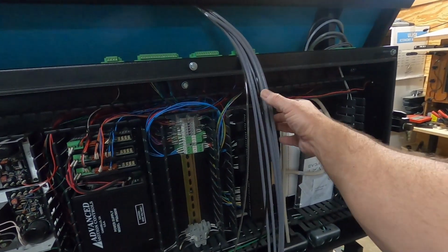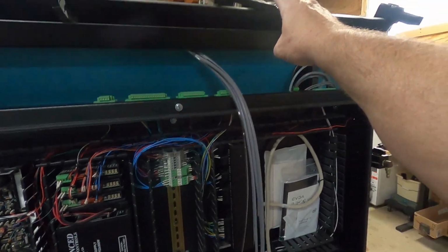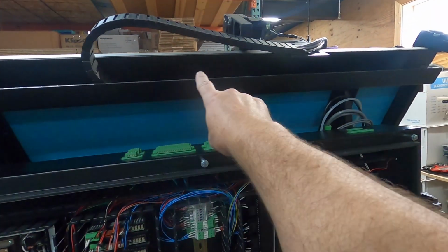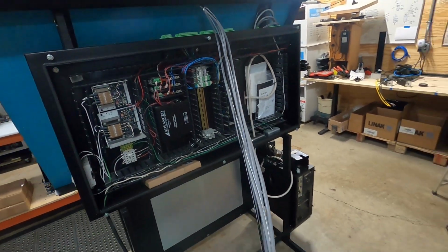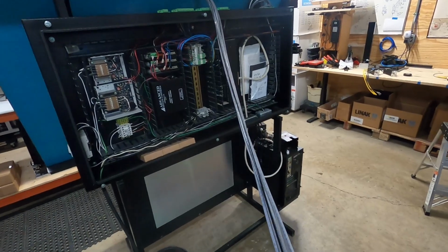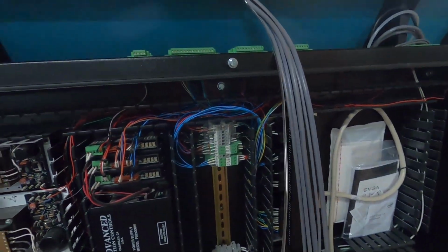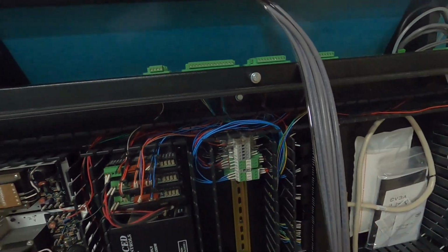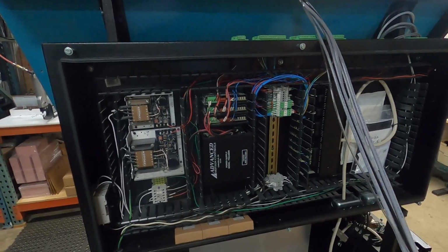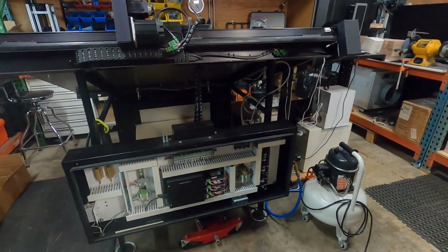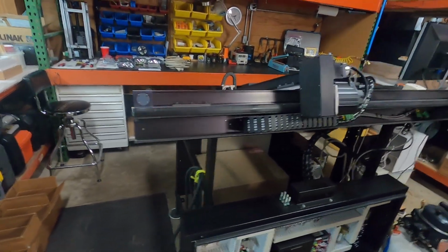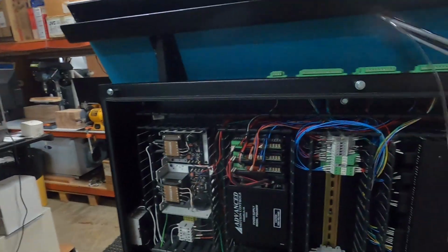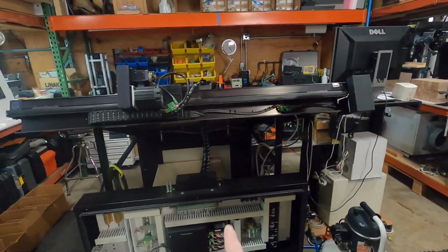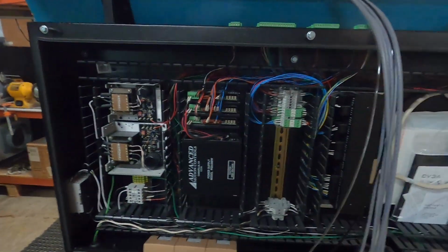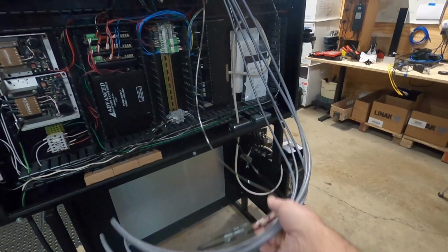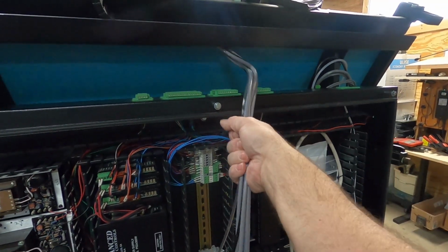Okay, so we've got all the wire in for the cutting head and the motor at the top of the arm, through this cable track right here. I've got a good amount of wire right here, about 5 feet. That's okay, because when I get done, it'll tuck back down behind the machine, so that if this machine ever decides to become a table style, like that machine, at a flat angle, there will be enough wire to reach the electrical panel when it's down here on the stand. So this extra wire is not a problem. Don't cut it off right here. Don't do it. Okay.